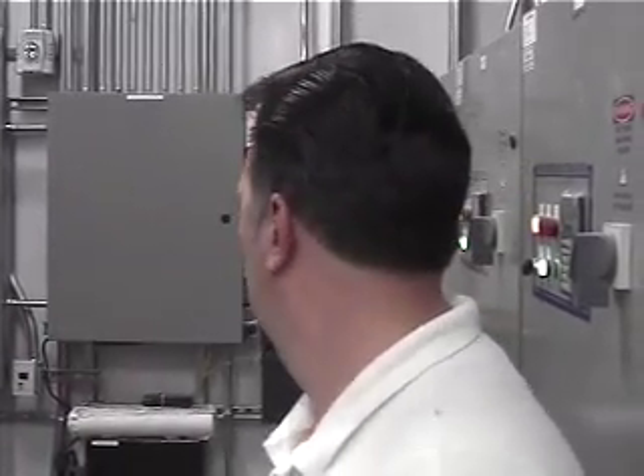You guys ready for me to turn this back on? When the generator fires up, it will keep two of them going to provide minimum exhaust. Is the UNC on generator power? Yes. All the DDC panels are on generator power. So when we shut off power, I went through and did an audit of everything. There were a couple of unit heaters and some little things like that that weren't coming up, but everything up here, all the humidifiers, anything we had to interface to, was on that panel. So pretty much everything that we need to see and stay up.